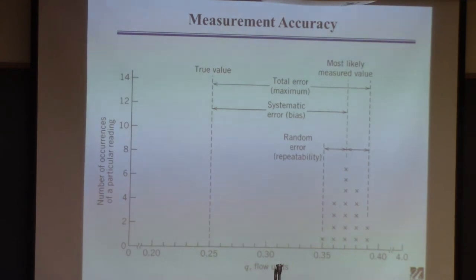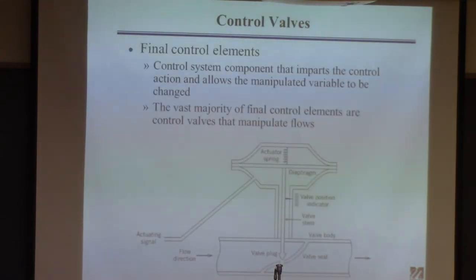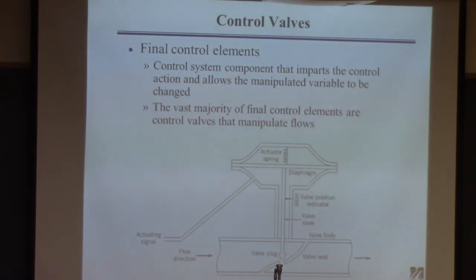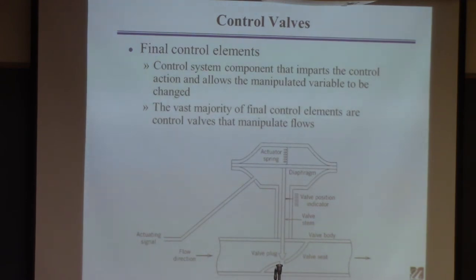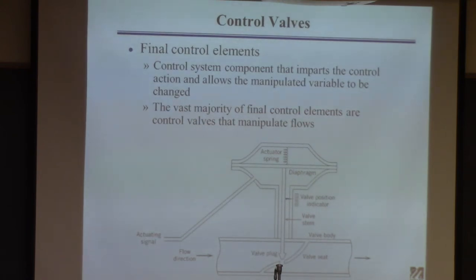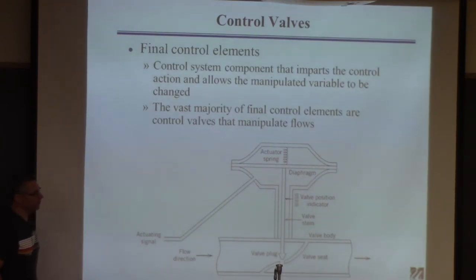So now on to control valves. If you have a control system operating in industry and it's not working, there's basically three main possibilities: the controller itself is poorly designed or poorly tuned; the sensor is not working, so you have a bad measurement coming into the controller; or finally, you don't have the ability to actuate correctly. If you go into a plant and look at what the controllers change to achieve control of temperature, flow, or pressure, it's almost always a control valve — I'd say 95% of final control elements are valves.